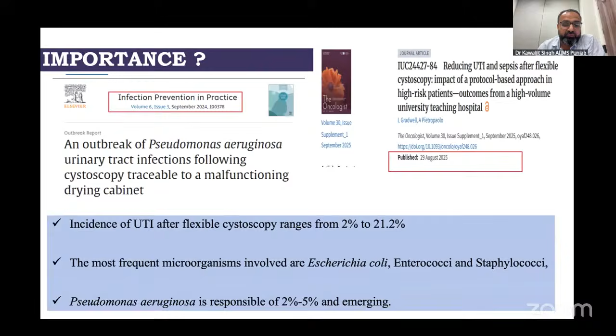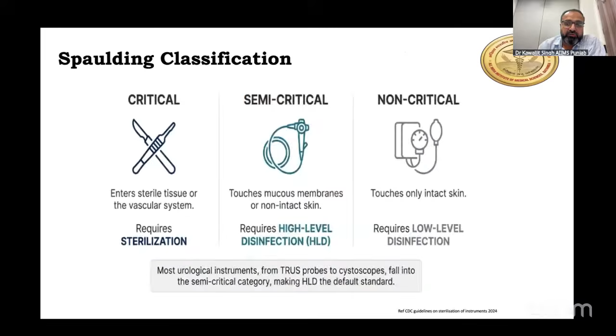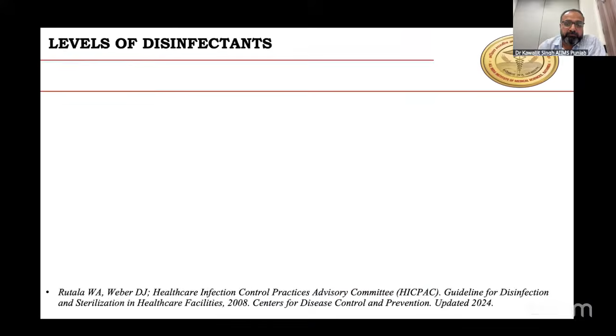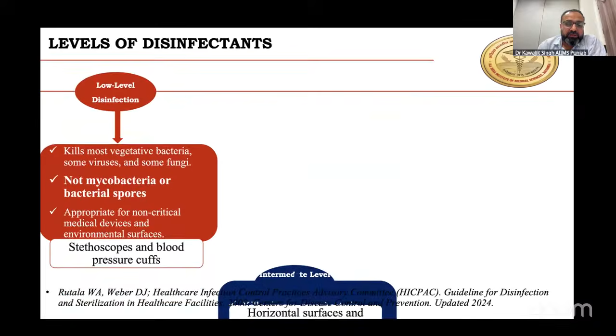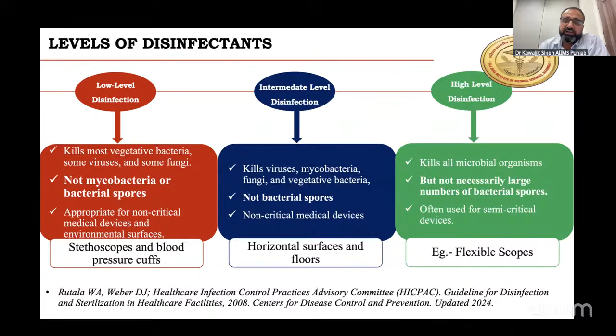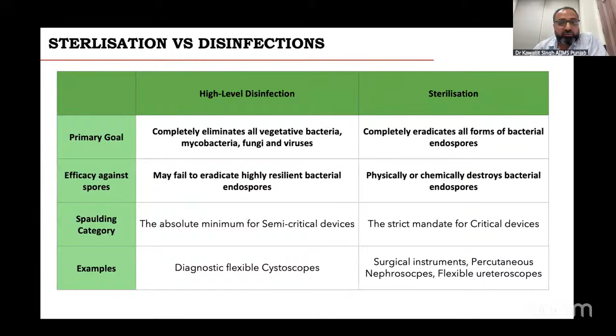Spaulding classification, I will not go into the detail, only focuses on semi-critical devices. Semi-critical devices is the category in which most of the urological equipment falls, and that is where lies the role of high-level disinfection, and that is what I'm going to focus on today. Quickly going to the basic difference between the high level and the other levels of disinfection: it kills more than 99% of the microorganisms, and some of the larger spores are left that cannot be disinfected with high level disinfection, and that requires sterilization. Sterilization eradicates all the endospores.